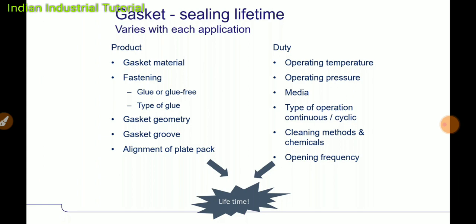And most of the time behind the gasket groove you will find pinholes where no chemical is going, but only glue is going. This kind of damage to the plate will have a very high impact on maintenance cost. Please use genuine gasket cement where chlorides are not there.